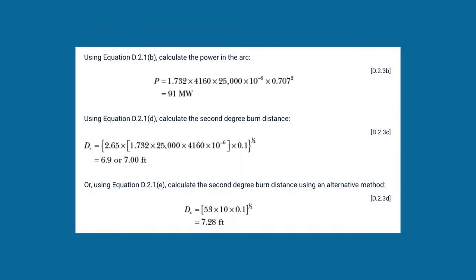Okay. Yeah, all that right there is two different ways to calculate your arc flash boundary when you're dealing with higher voltages. So that arc flash boundary, how does that relate with the limited approach and the restricted approach? The limited approach and restricted approach, that's in 130.4 D, A, and B. And that's for shock protection. And for shock, at the very minimum, that's going to be your barricade.